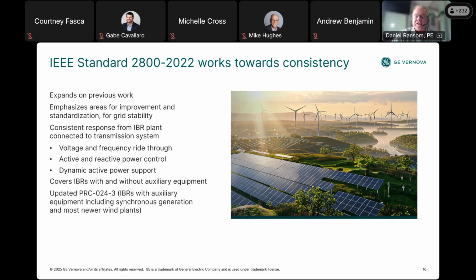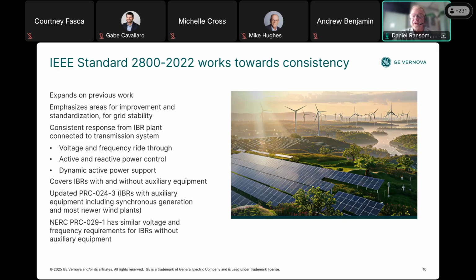IEEE 2800-2022 covers IBRs with auxiliary equipment and without auxiliary equipment. It includes the NERC equivalents of PRC-024-3 and PRC-029-1. The updated PRC-024-3 covers IBRs with auxiliary equipment, including synchronous generation and most newer wind plants. And NERC PRC-029-1 has similar voltage and frequency requirements to 2800 for IBRs without auxiliary equipment.